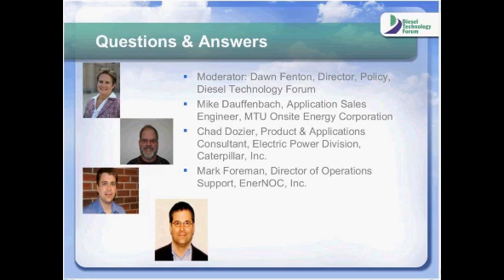The 30% is a rough average of what we see. In an islanding situation, what you get is whatever load the customer has put on that backup generator. When the generator was installed, the customer wires certain electrical panels into the emergency power system for that facility, so whatever's on that emergency power is what the generator will carry. Our experience shows that customers often don't put all the systems in their building onto emergency power. An office building, for example, might not anticipate being occupied for many hours on backup power.